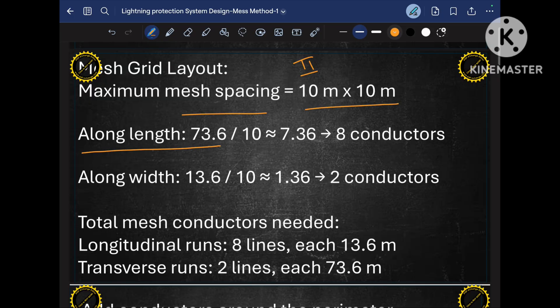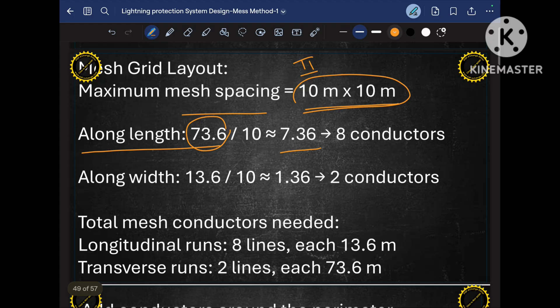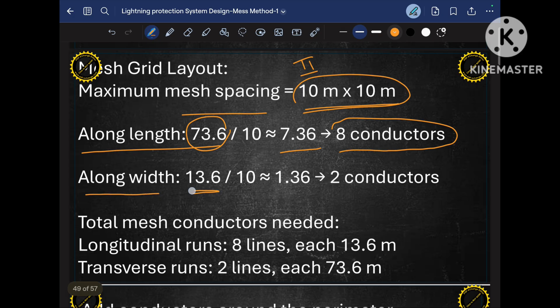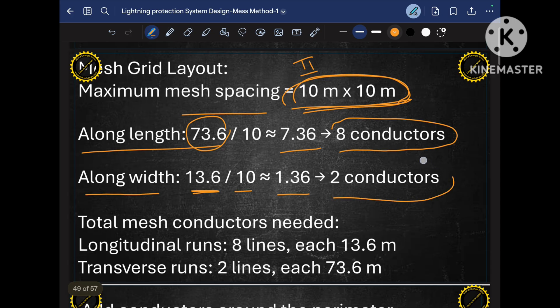Along the length, since the building length is 73.6 meters, we divide by 10 because our MESH size is 10m x 10m. That gives approximately 7.36, so along the length we need 8 conductors. In the same way, along the width — the width of our worker accommodation is 13.6 meters — we divide by 10, giving 1.36. So approximately we need 2 conductors along the width.